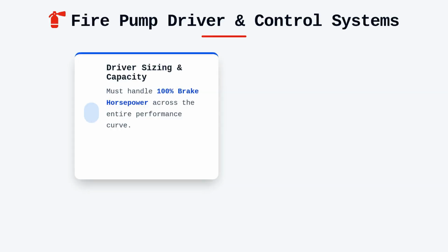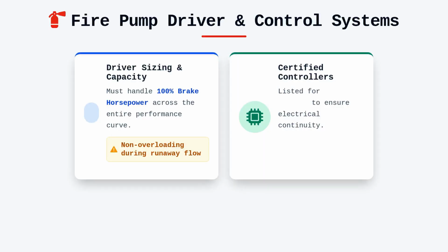Beyond the pump itself, the driver, whether electric motor or diesel engine, must be sized to handle 100% of the pump's brake horsepower at any point on the performance curve. We often overlook the fact that a fire pump can experience a runaway flow condition, which shifts the motor toward its maximum power output. Therefore, the driver must be non-overloading at any point. Electric motor controllers and diesel engine controllers must be listed for fire pump service to ensure that essential electrical supply circuits remain energized even when other building systems are tripped.